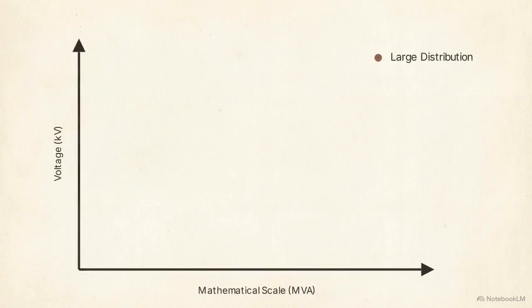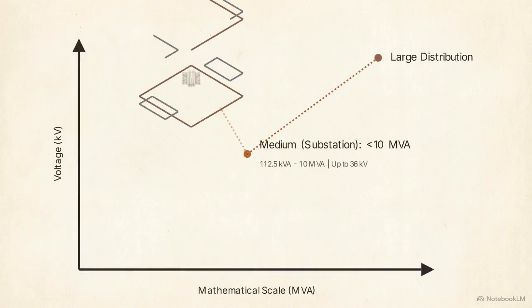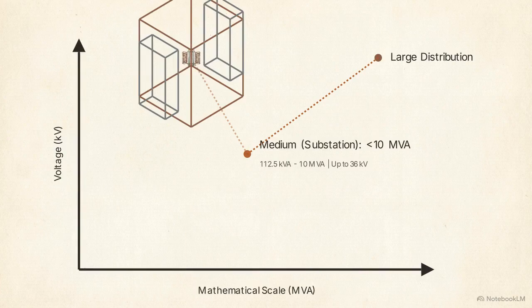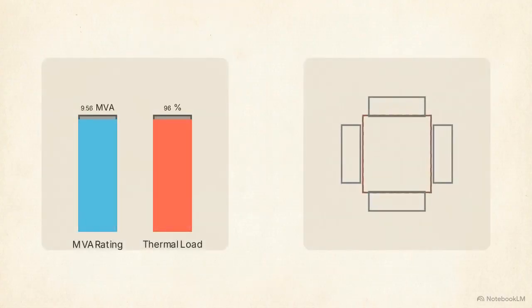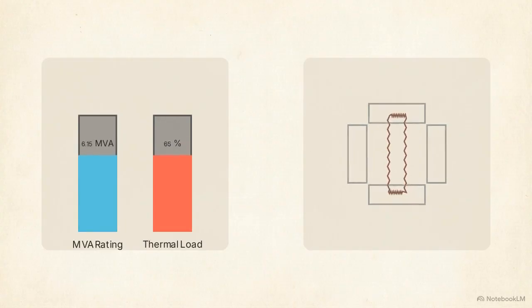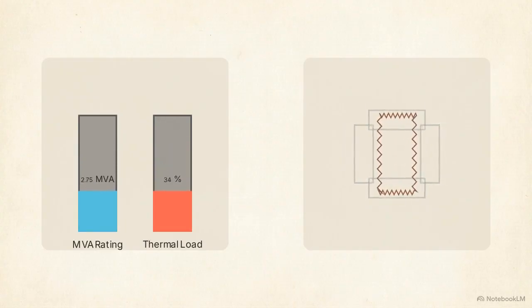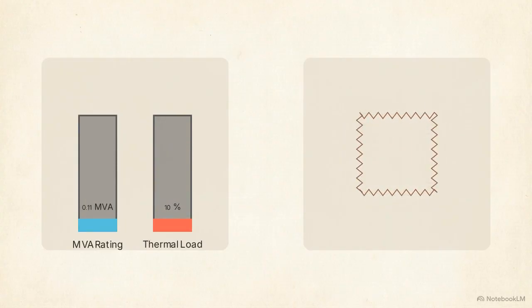Moving down the rating scale brings us to the local grid nodes. The medium or substation class metrics drop from 10 megavolt amperes down to 112.5 kilovolt amperes, handling up to 36 kilovolts. There is a direct physical correlation. As the megavolt ampere rating drops, the internal thermal load decreases, and the external cooling footprint naturally contracts to match it.